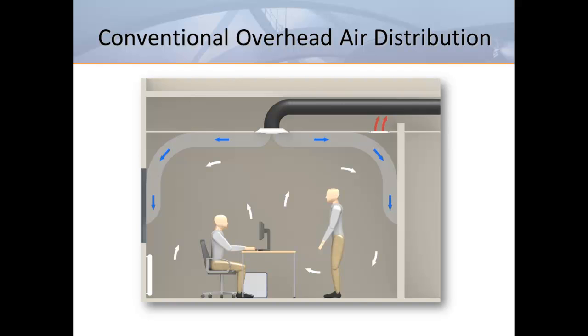We should start by explaining the difference between conventional overhead systems and displacement ventilation. Conventional overhead systems provide comfort through room air mixing — for this reason, these systems are also known as fully mixed systems. In typical cooling applications, 55-degree air is supplied from ceiling diffusers or high sidewall grills. The induction created by the outlet discharge jet results in room air motion, with secondary air motion due to the entrainment of room air into the supply jet where mixing occurs. Ideally, an overhead system results in fully mixed air throughout the occupied zone with minimal temperature stratification.